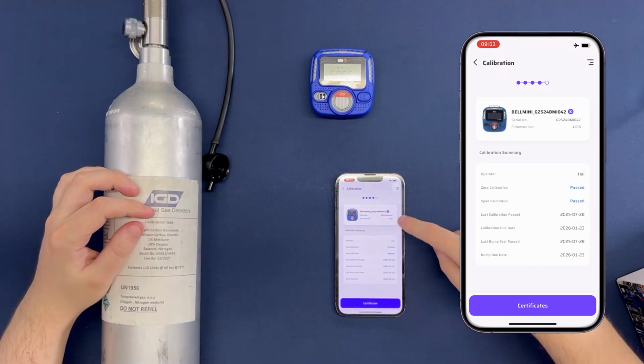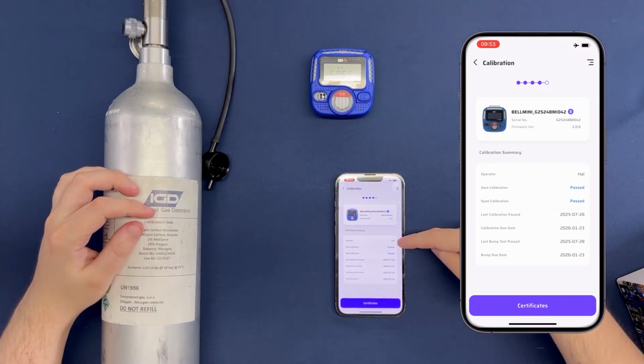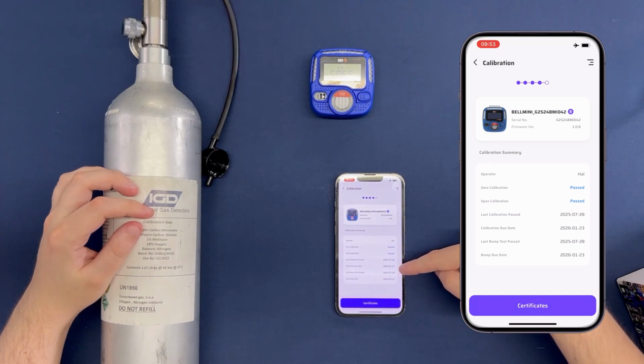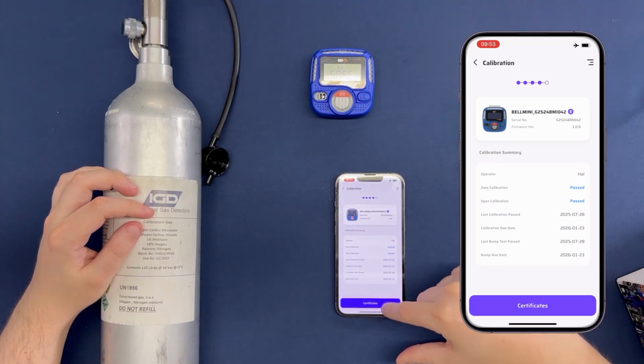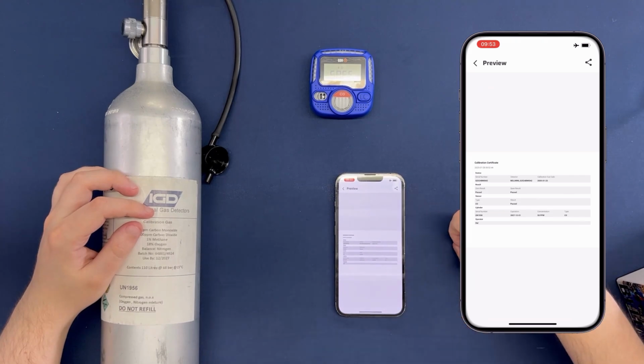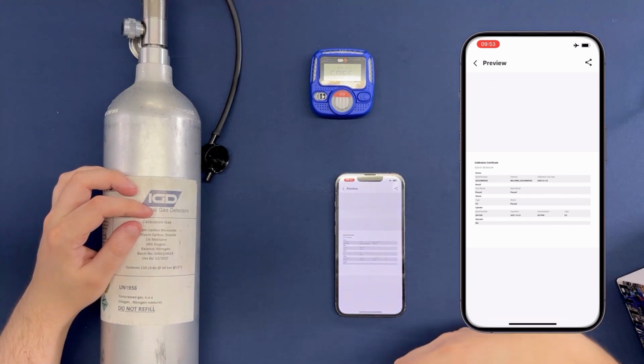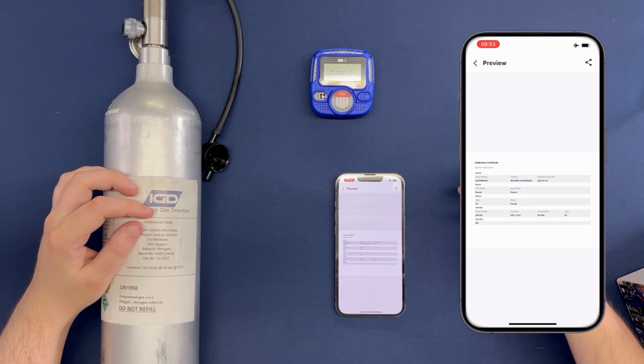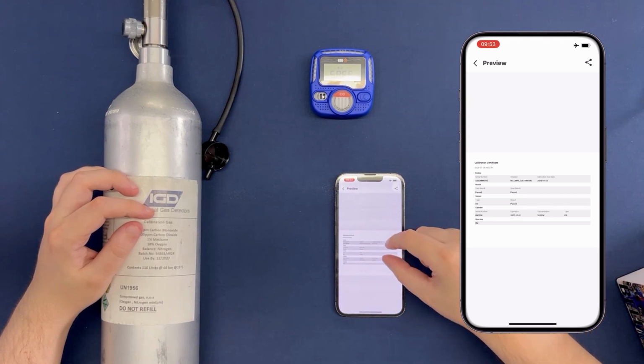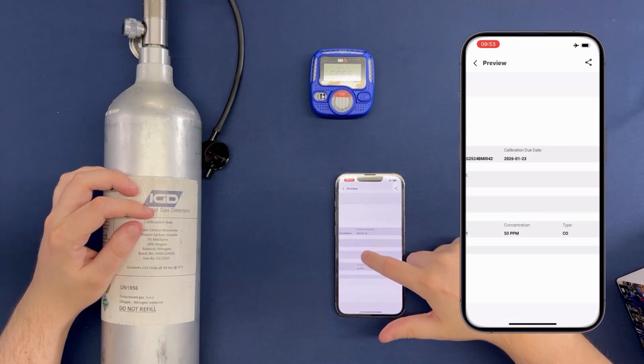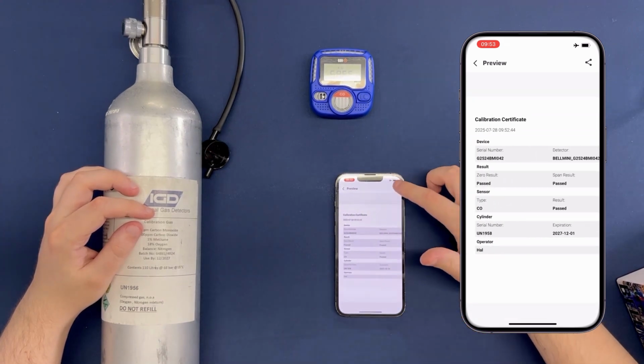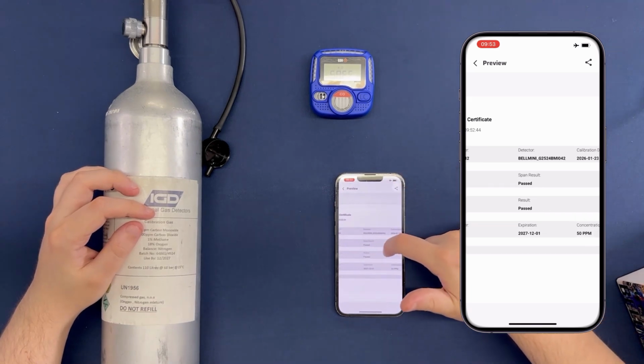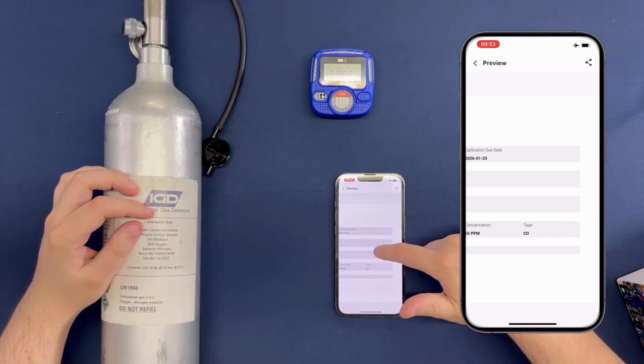On the calibration certificate, you'll see that we've passed both of these. We've got the operator name as well that we've inputted before, and we can also see when the next calibration is due. If we look at the certificate, the BELLMINI will also produce a certificate, and all that information we put at the start, the engineer's name, the calibration gas bottle, the gas level, and the expiry date, all gets automatically filled out on this calibration sheet. And again, by clicking the export button at the top right, you can send that as a PDF to your email and send that out.